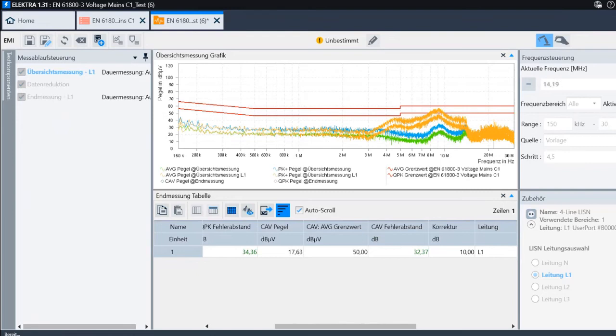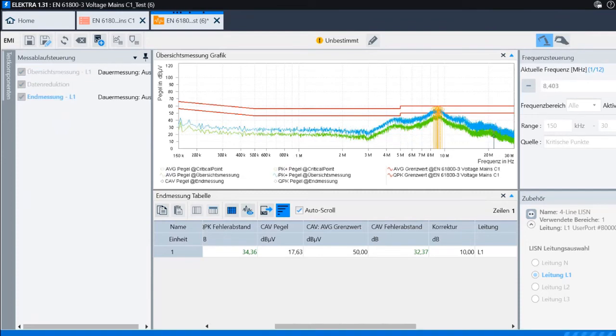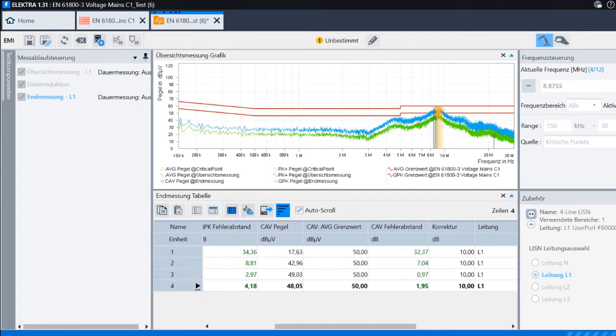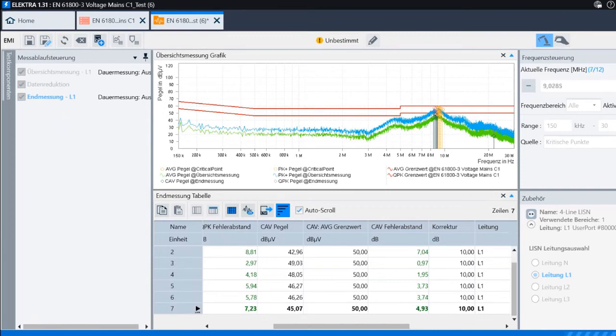So now we are looking at different kinds of shielding attached. What you see in the green and blue is the old measurement which we saw before, and now it changed again to green and blue, the peak and average measurement, and we see now this is the measurement without shielding on the motor side. So it changed quite heavily for the upper frequencies.